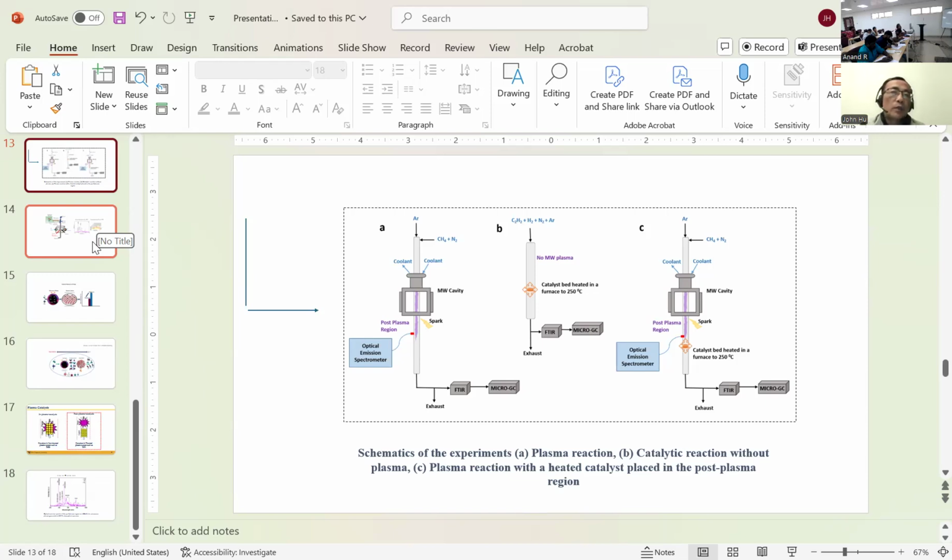Don't buy those for liquids, because the OES will not see liquid drops. It will only see the plasma species. It has to be in the gas phase. That means the molecules will be very small. Typically, you will know methane, ethane, and ammonia, whatever you name. Those are small molecules. Yeah, CO2, you will see it.